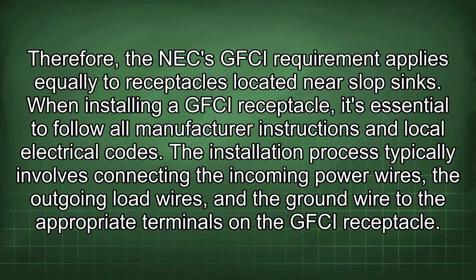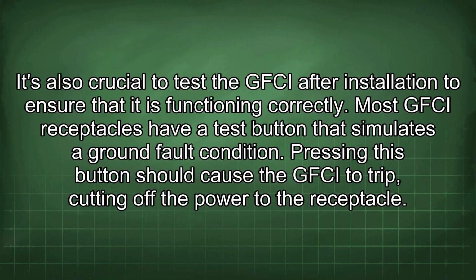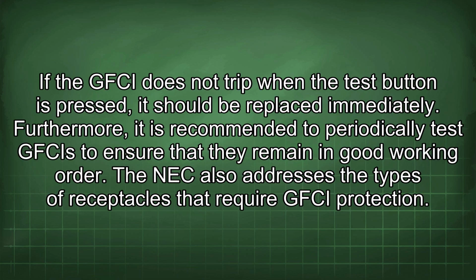When installing a GFCI receptacle, it's essential to follow all manufacturer instructions and local electrical codes. The installation process typically involves connecting the incoming power wires, the outgoing load wires, and the ground wire to the appropriate terminals on the GFCI receptacle. It's also crucial to test the GFCI after installation to ensure that it is functioning correctly. Most GFCI receptacles have a test button that simulates a ground fault condition. Pressing this button should cause the GFCI to trip, cutting off the power to the receptacle. If the GFCI does not trip when the test button is pressed, it should be replaced immediately. Furthermore, it is recommended to periodically test GFCIs to ensure that they remain in good working order.